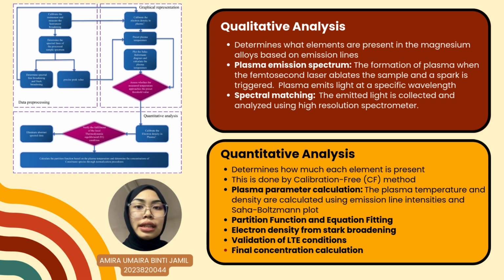Next, this light is collected and analyzed using a high-resolution spectrometer. By performing spectral matching, we compare the detected wavelengths to known standards, which allows us to accurately determine which elements are present in the sample. This process is highly sensitive and precise, making it a powerful tool for elemental analysis in complex materials like magnesium alloys.